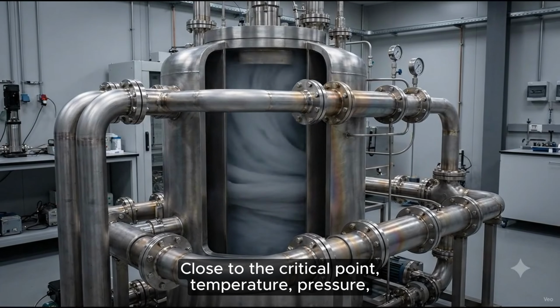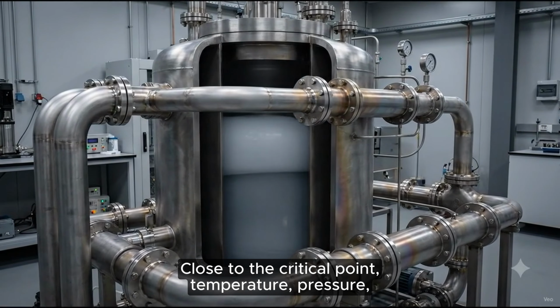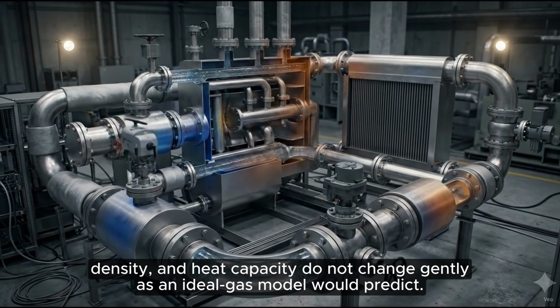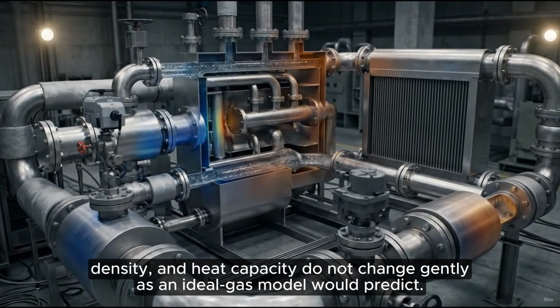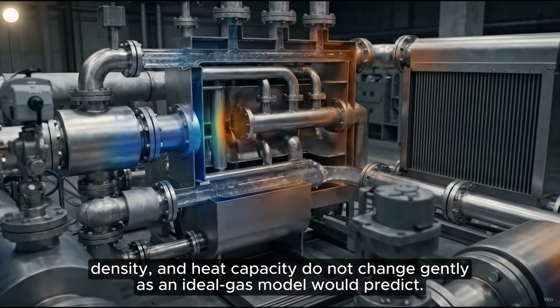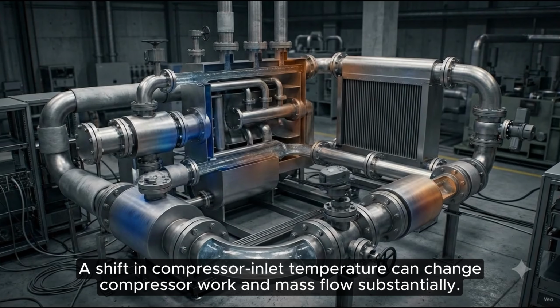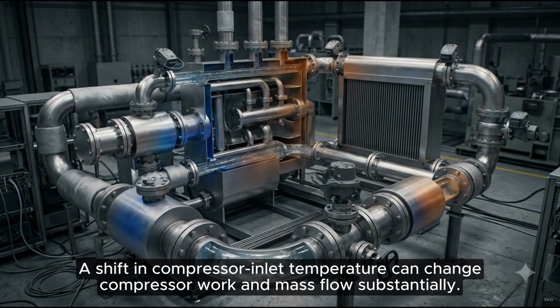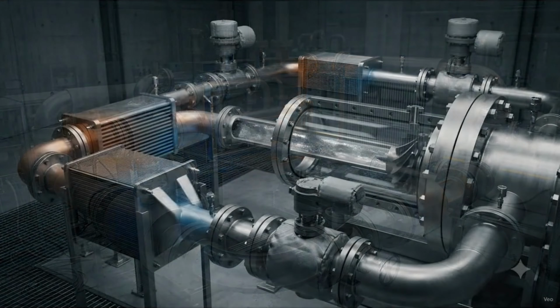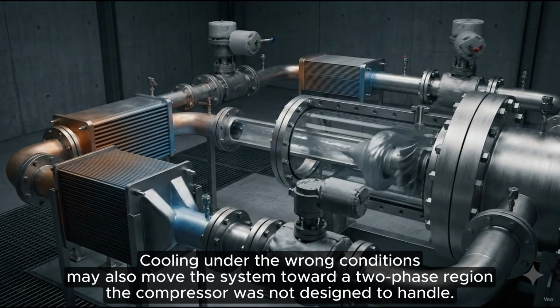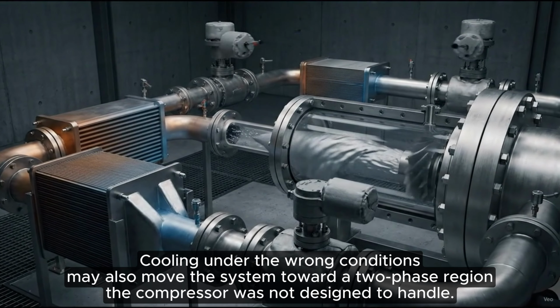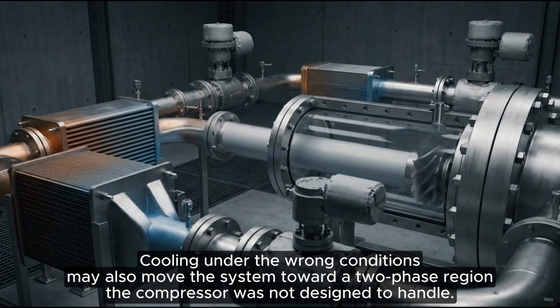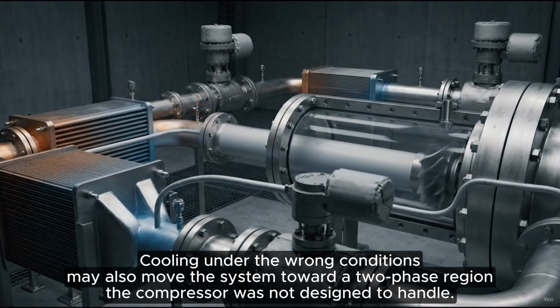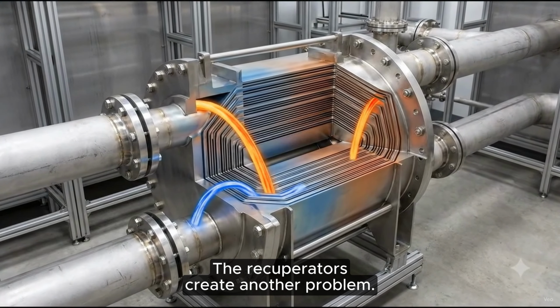Close to the critical point, temperature, pressure, density, and heat capacity do not change gently, as an ideal gas model would predict. A shift in compressor inlet temperature can change compressor work and mass flow substantially. Cooling under the wrong conditions may also move the system toward a two-phase region the compressor was not designed to handle. The recuperators create another problem.